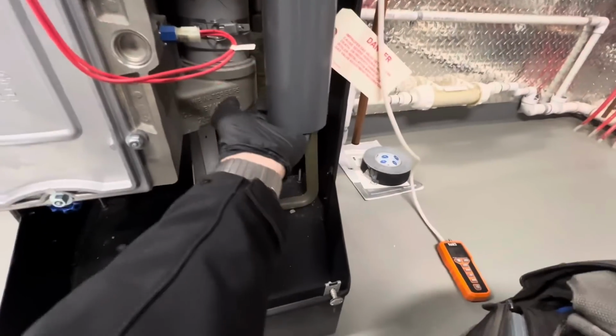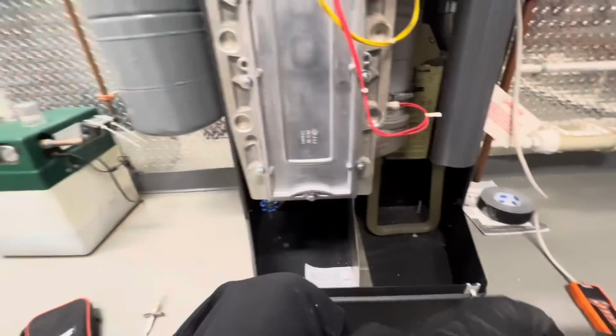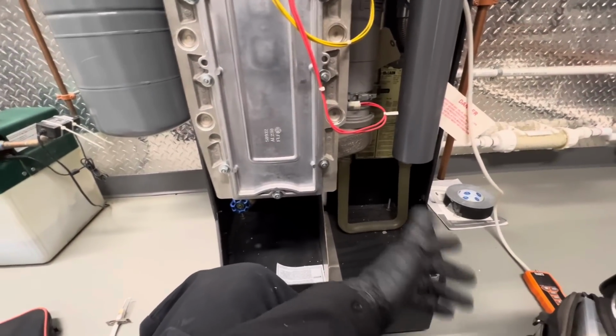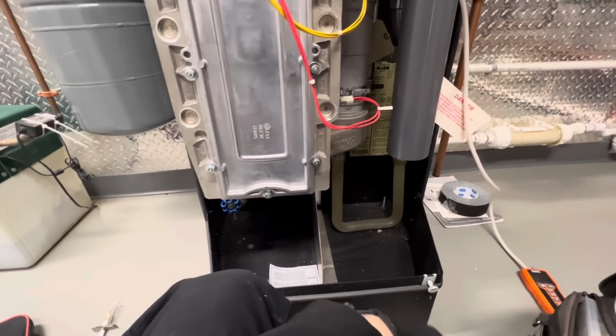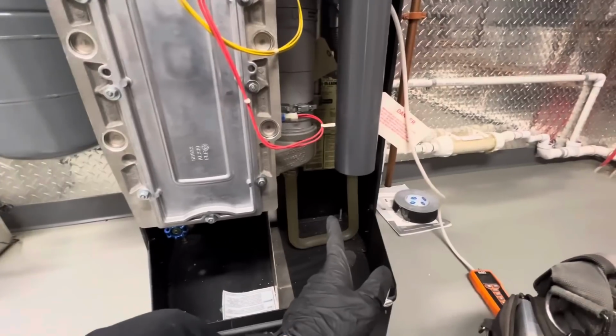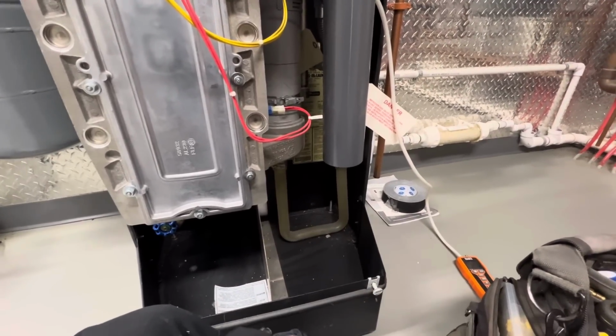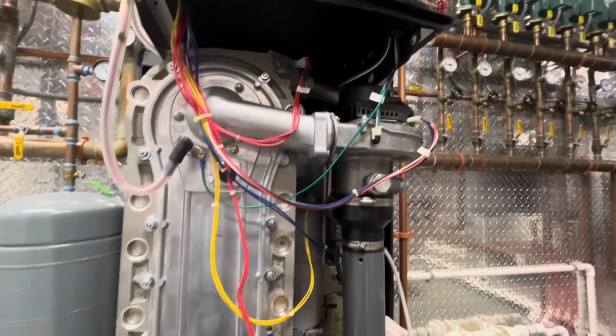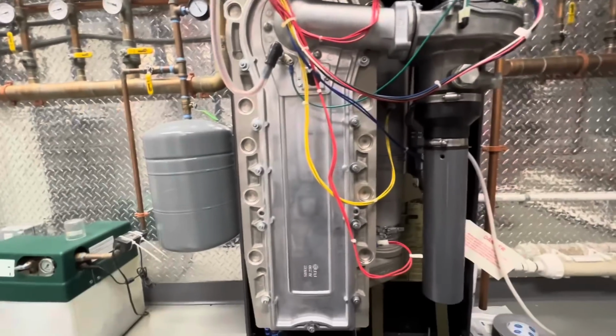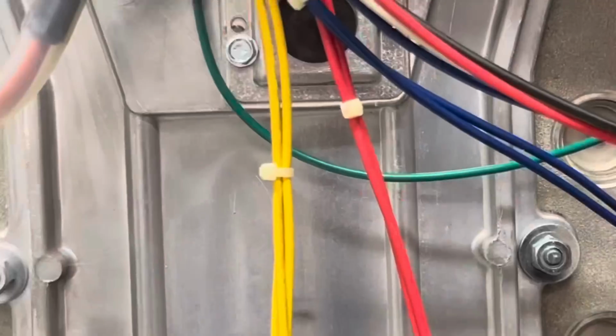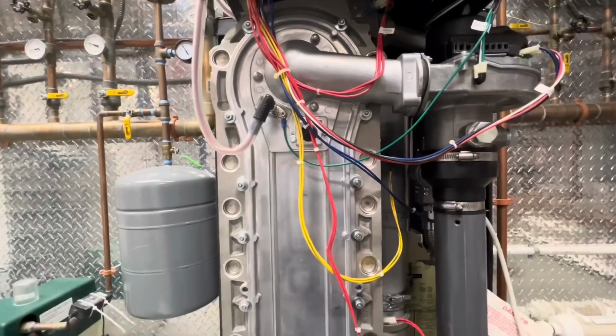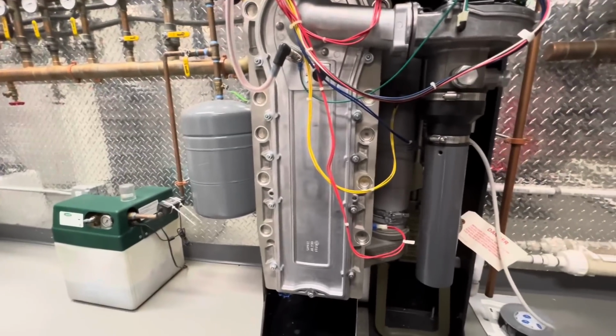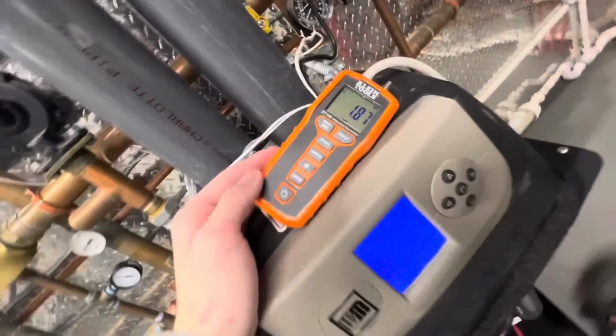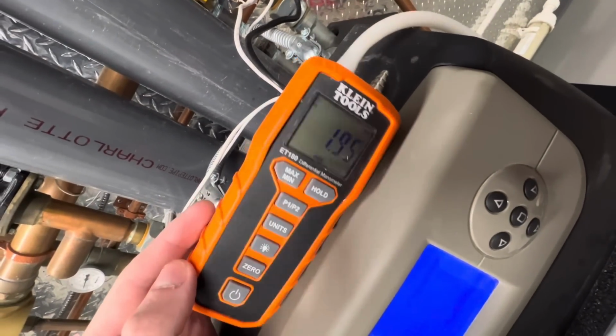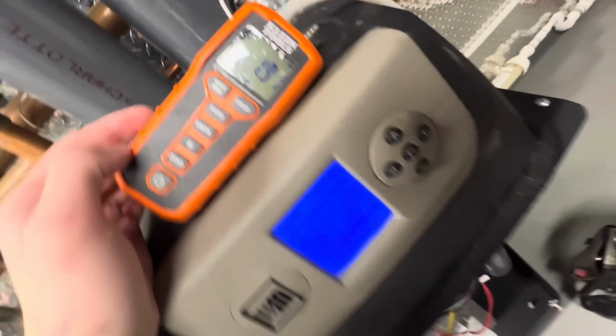Because as you saw, maybe there was a piece of electrical tape here that I took off. That's what they were using to keep this running, but we want that fuel air mixture to be right, so if we still have a gas pressure issue, then they're gonna have to address that. But we'll see what happens when we get it kicked on and everything like that. It was really disappointing that that snapped and that's the way that I had to get this running. But sometimes you just have to do what you have to do. And our gas pressure bouncing around, but really low.